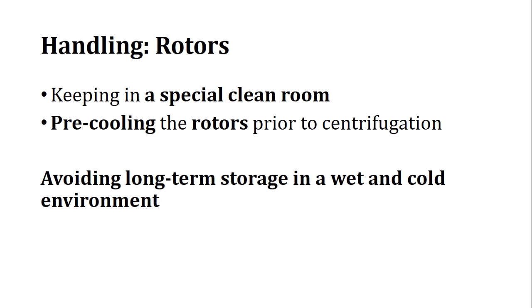The rotor should be kept in a special clean, dry room or space. Pre-cooling of the rotor prior to centrifugation is a recommended technique. Long-term storage in a wet and cold environment should be avoided. The researcher should personally observe and follow all these precautions.